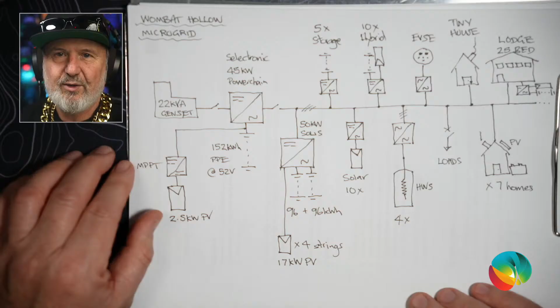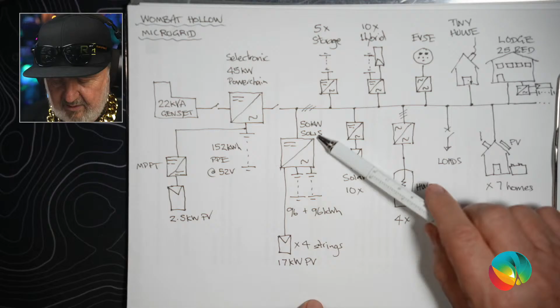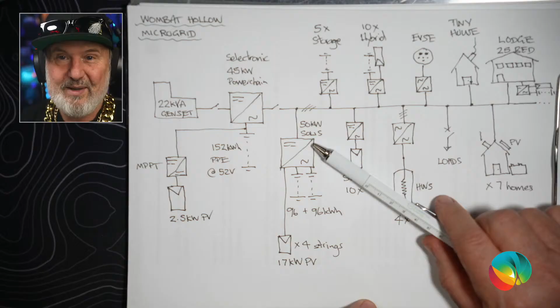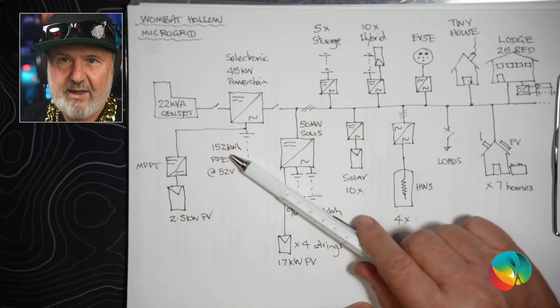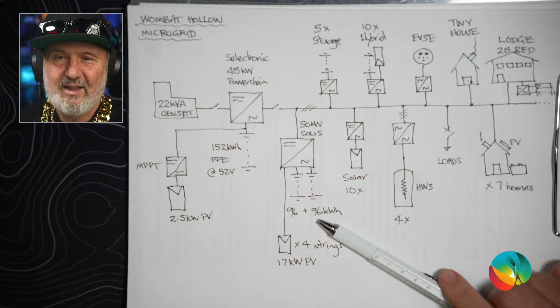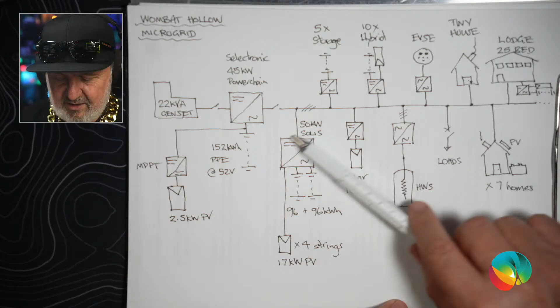So yeah, this section here is our microgrid forming system. Now, recently we've added a 50 kilowatt hybrid inverter to the mix. That's a big step up, I can tell you, from having 152 kilowatt hours to, at the moment, about 200 kilowatt hours connected to this hybrid inverter, but soon it'll be up to 800 kilowatt hours connected. We've got to connect another 6 stacks of batteries. So how did I integrate this? Well, this is where AC coupling is an amazing thing.